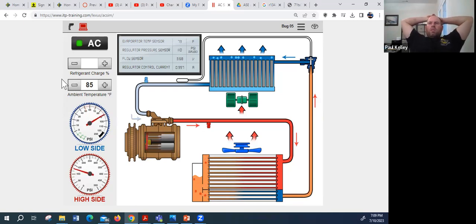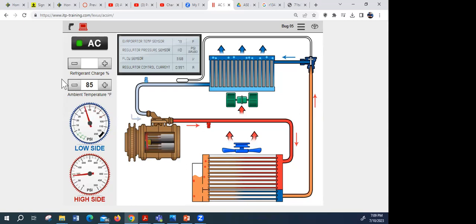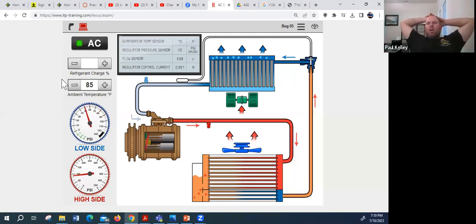So what would we consider this to be doing? What is happening there, jumping up? Pressures are fluctuating. Yeah, could be air in the system, but I also want to point out it kind of seems like that compressor clutch may be cycling. There's a term for that, it's called short cycling. The AC compressor kicks on, runs for a little bit, sees the pressures don't really spike up as high as they should, so it thinks it's low on refrigerant. To protect itself from damaging the compressor, because if it's low on refrigerant there's nothing to carry the oil around for lubrication, it'll shut off. It'll try again, shut off. Try again, shut off. That's kind of what I'm thinking, but I'm not sure.